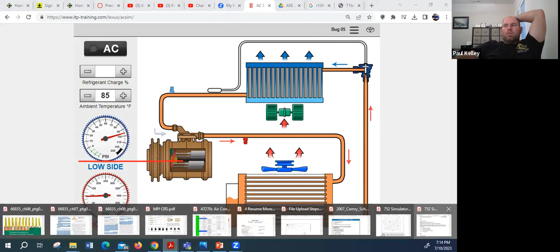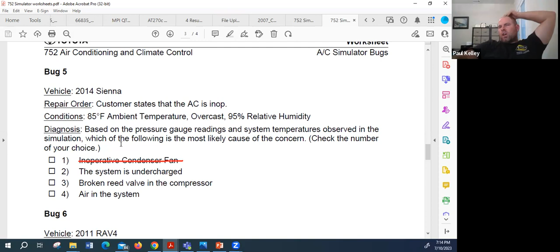But if the system is undercharged, it will cause it to short cycle like that. But then, check the static pressure, and the static pressure is good, so there's no reason to think it's undercharged, right? Yeah, you can cross that one out. You follow me, so I don't think it's undercharged because the static is good.